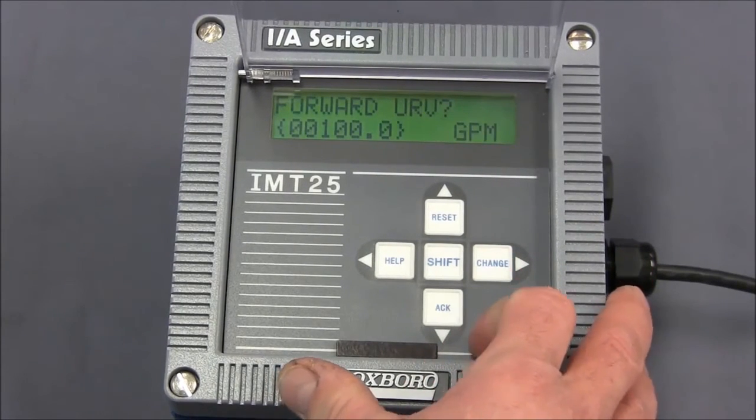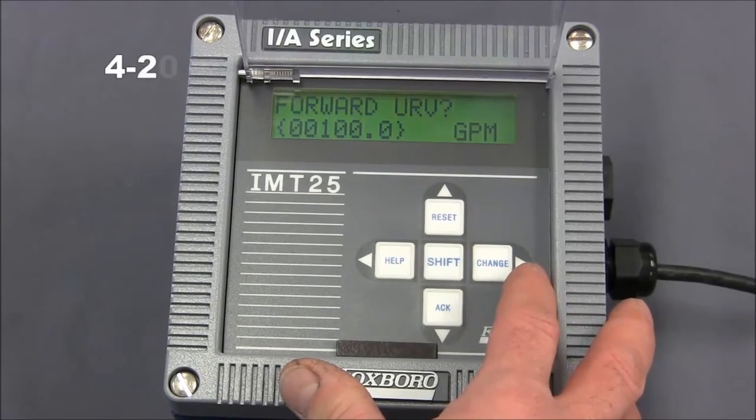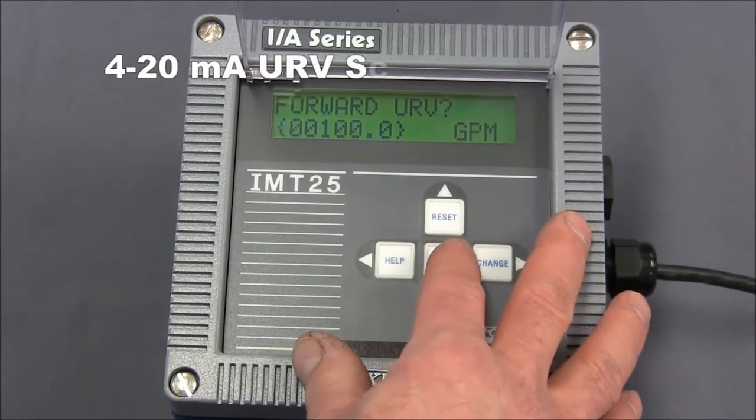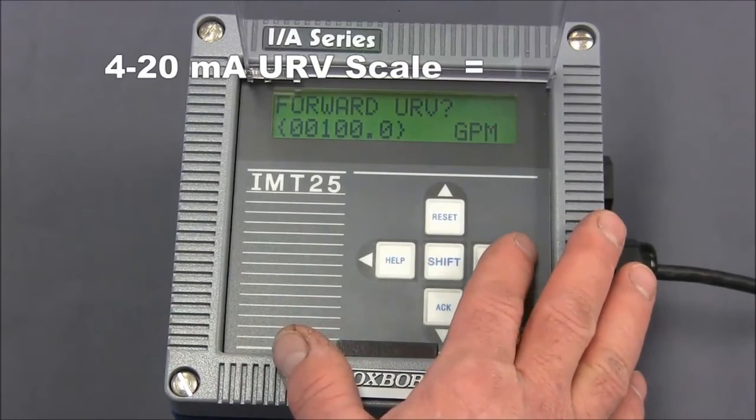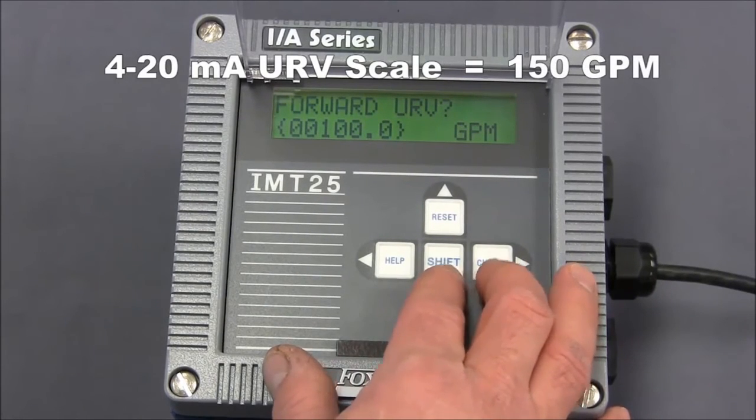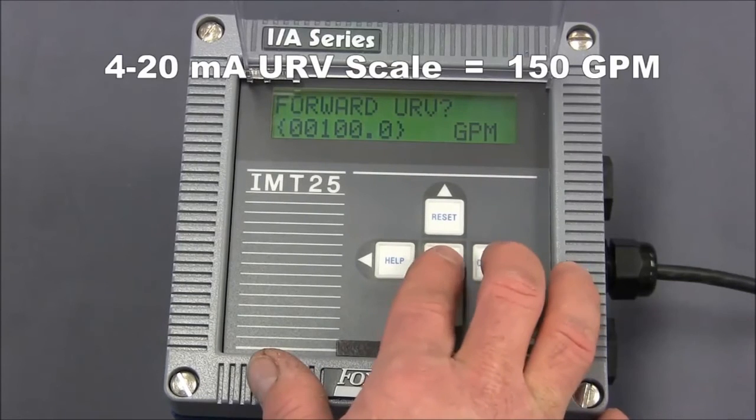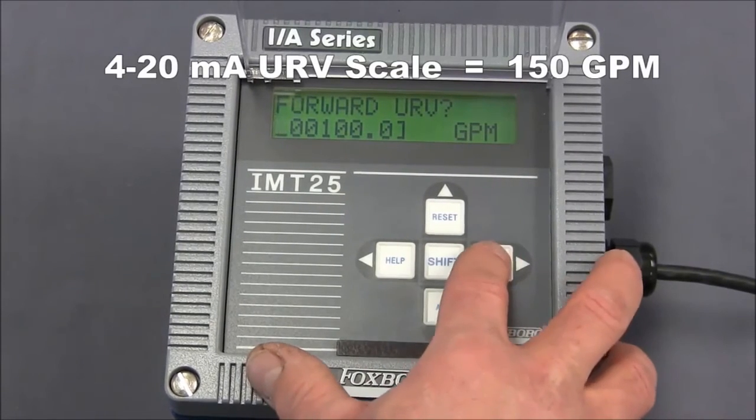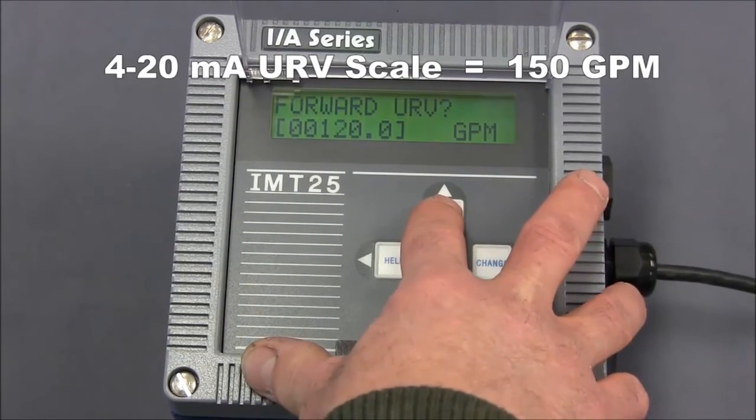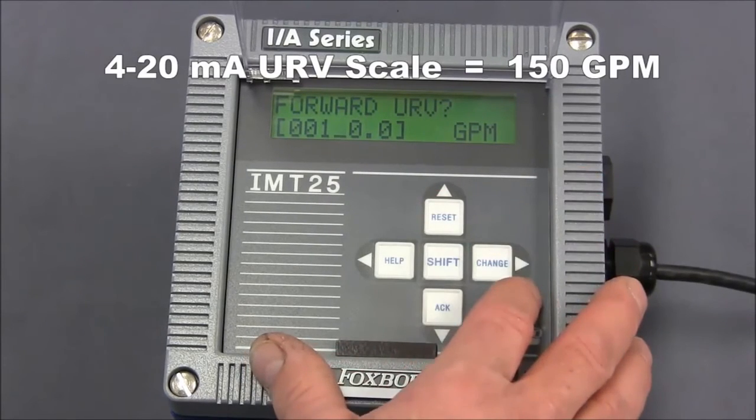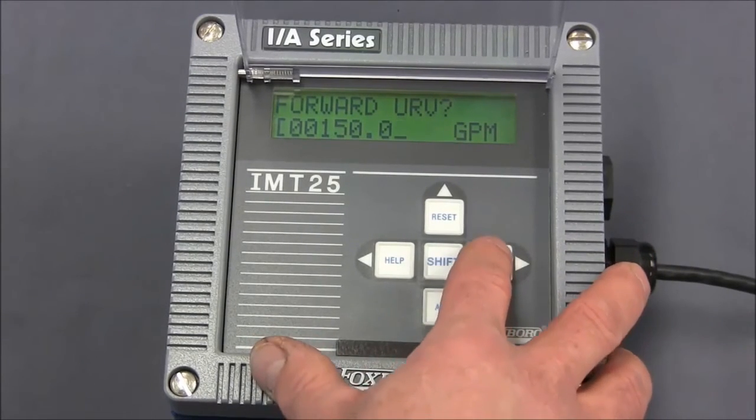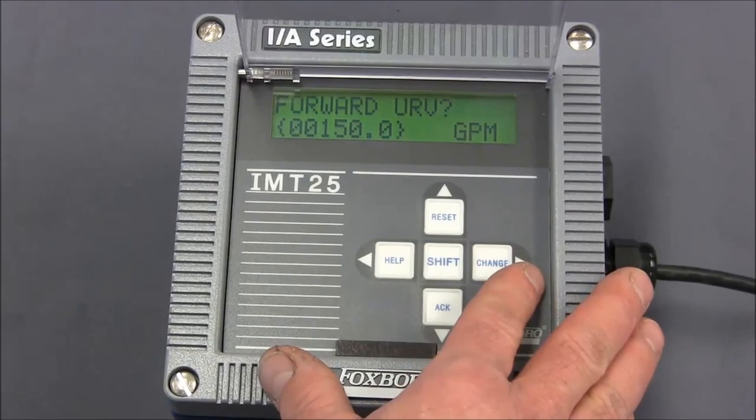Hit the right arrow again and here is our forward URV. This is our 4 to 20 milliamp scaling value. Four is always zero flow and whatever value here we enter is our 20 milliamp point. For this exercise we're going to change this to 150 gallons a minute. So we'll do shift and change, move along using the right arrow key to get to the tens position and we'll make that into a five. Go to the right and continue to the right until we get the right bracket flashing. We press the right arrow one more time and that locks this value in place.